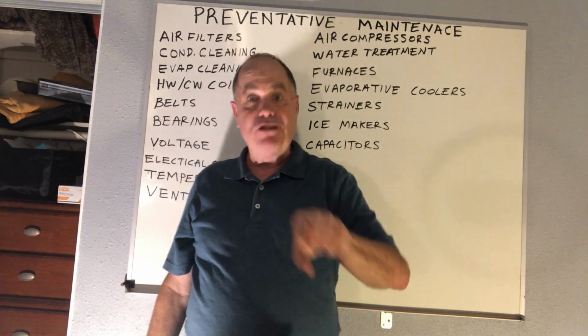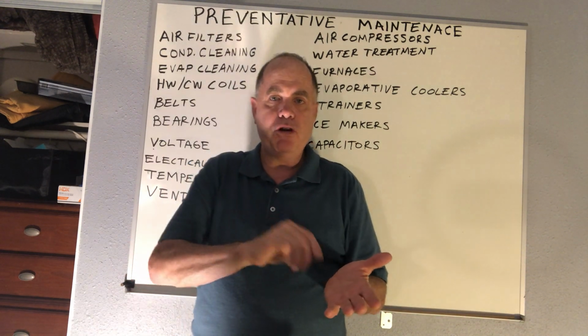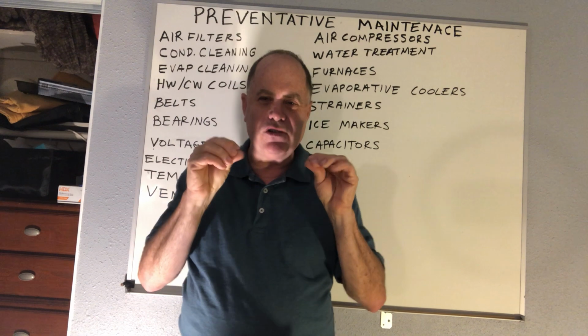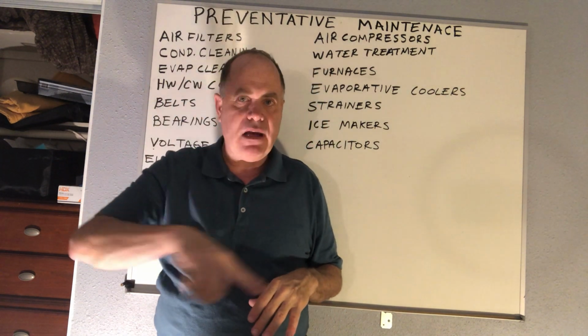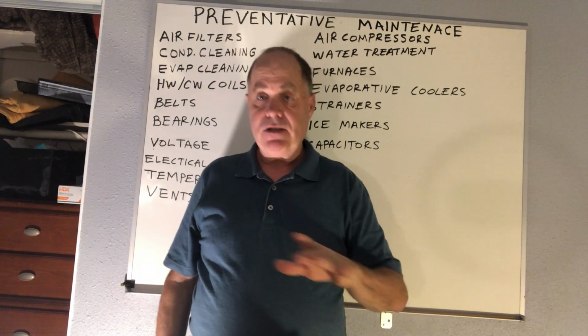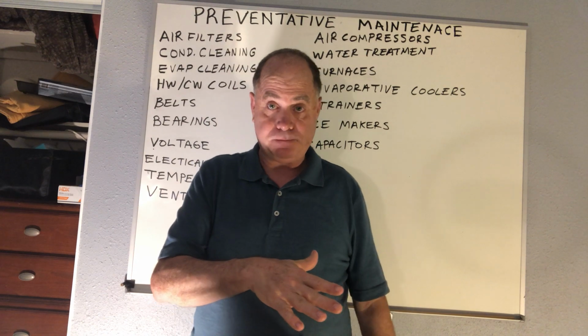Cleaner is descaling. So you actually sometimes will take a little toothbrush or something and put a stronger concentration and go over some parts of your evaporator and other parts of your drain pan that have these minerals stuck to it. Then you run the pump and clean up that scale and flush it all out many times. Sometimes it's good to do this when the ice maker's empty, because then you can also clean the bin. Put a little bit of bleach or ice machine cleaner in the bottom of the bin and rinse that down, just to have everything clean.